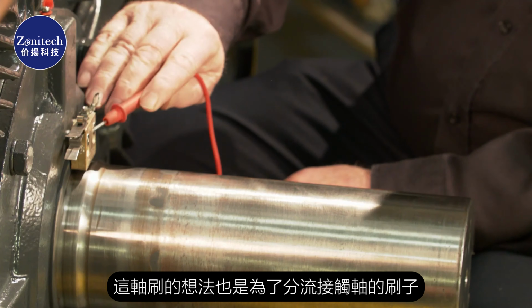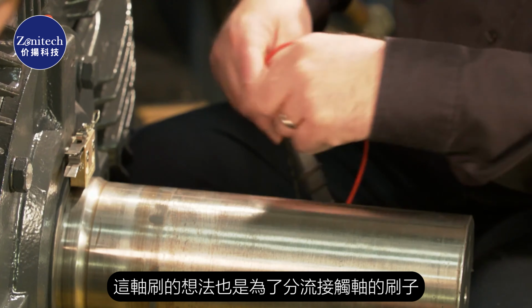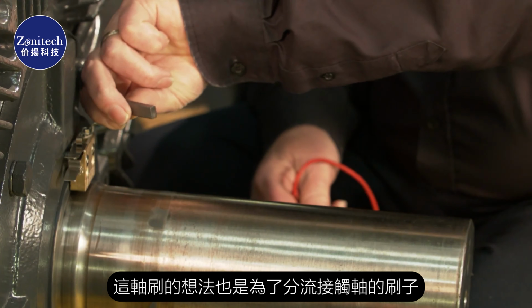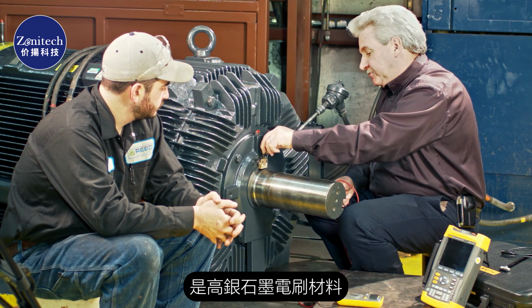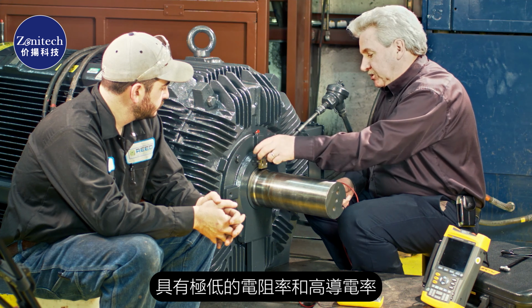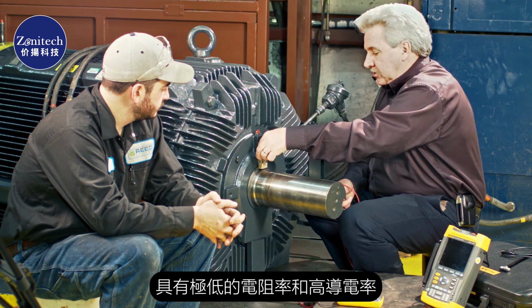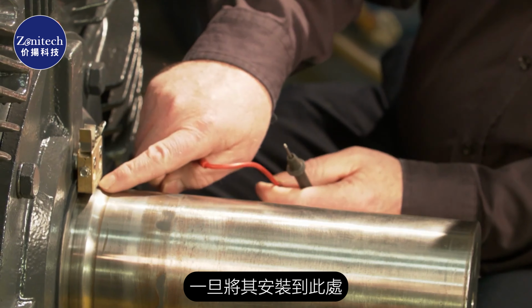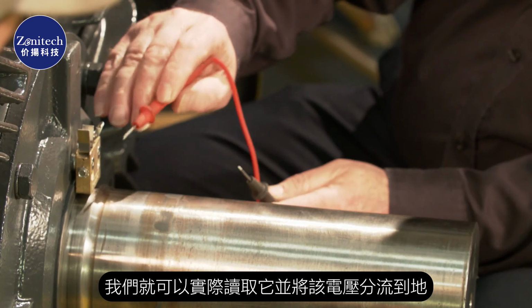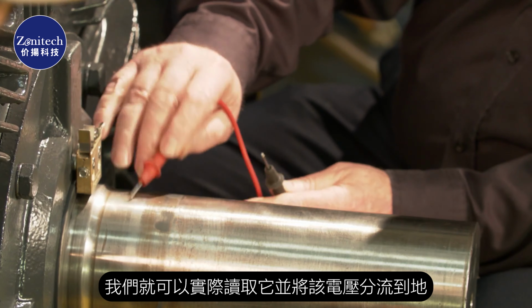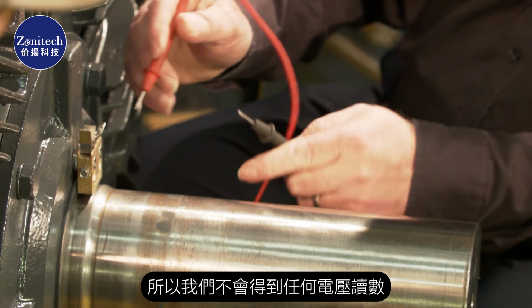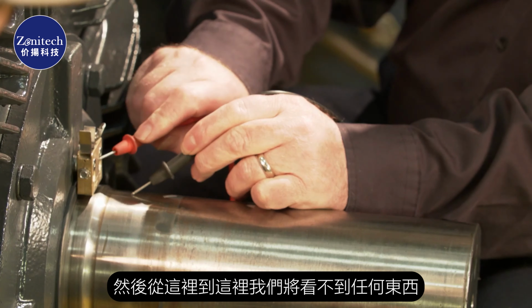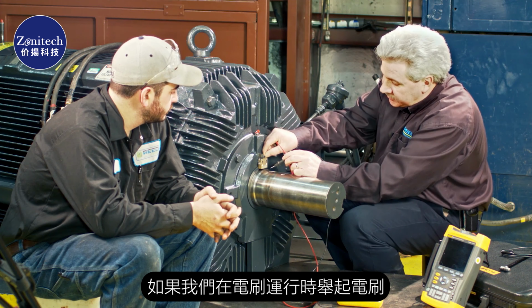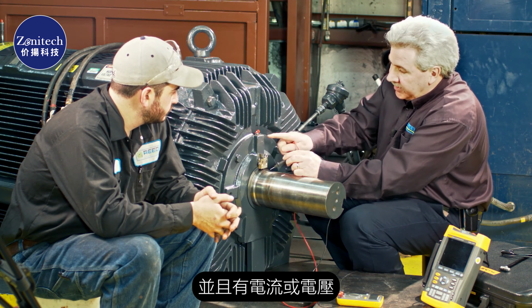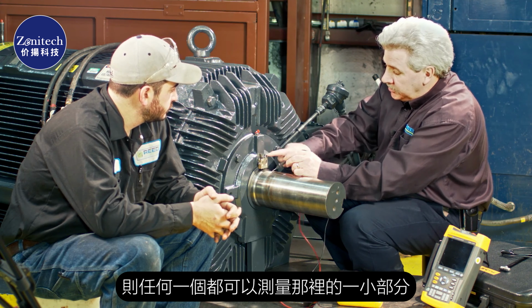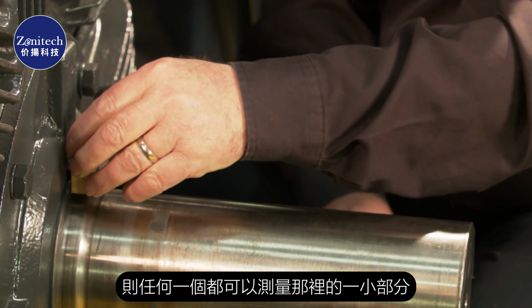The idea of this shaft brush again is to shunt the brush touching the shaft. It is a high silver graphite brush material, which has an extremely low resistivity and a high conductivity. Once it's mounted to this right here, we're able to actually read it and shunt that voltage across the ground, so we won't get any voltage readings then. From here to here, we won't see anything. If we lift up the brush when it's running, if we have a current or a voltage, either one, we'll be able to measure a small amount across there.